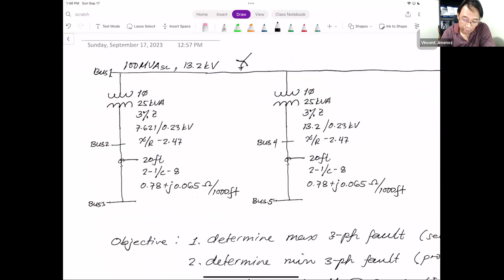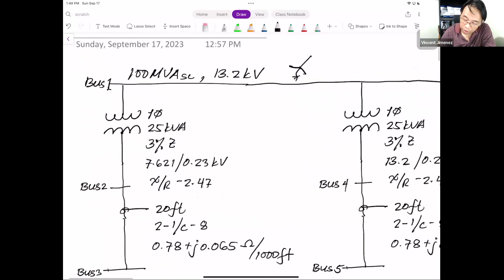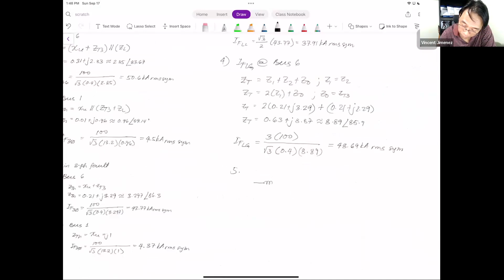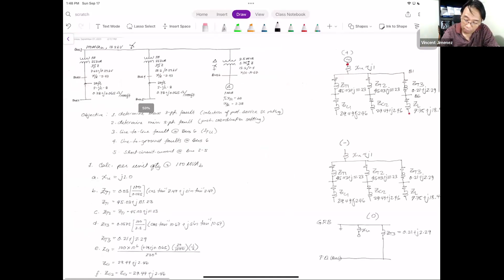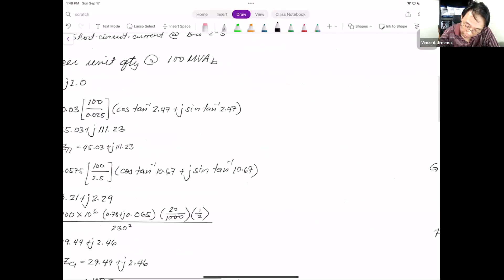To represent our first transformer connection, this is connected line-to-neutral. If we represent our system using the maximum fault, this represents our three-phase system at the utility. The single-phase transformer is connected via neutral since our voltage is 7.621, which is the line-to-neutral voltage — that's where our transformer connects.